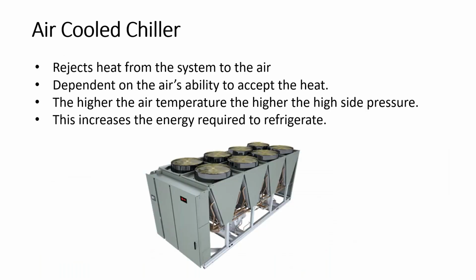So, an air-cooled chiller, a little more detail. This is a packaged piece of equipment. It rejects the heat from the system to the air on the condenser side. It's dependent on the air's ability to accept that heat. So 75-degree day, no problem. We're going to blow air across these coils and we're going to pull all the heat out of the refrigerant and condense, and we've got no problem. But on a 105-degree day, it's going to be tough because you've got to get the refrigerant up above that to reject the heat to the air. So the higher the outside air, the more work we're going to have to do no matter what.